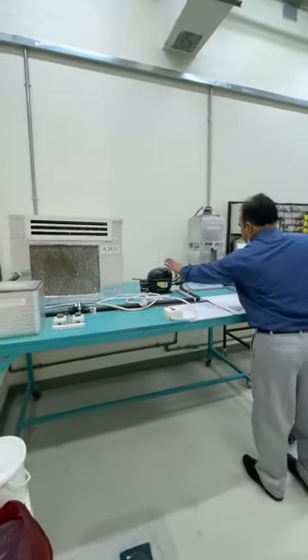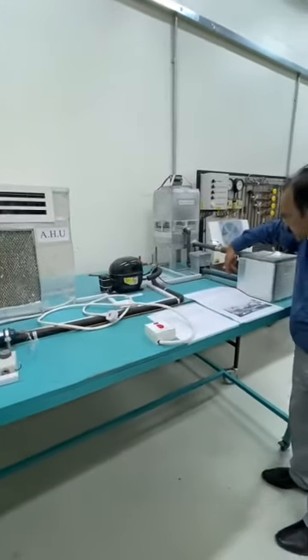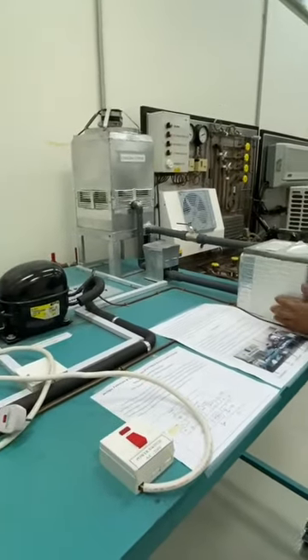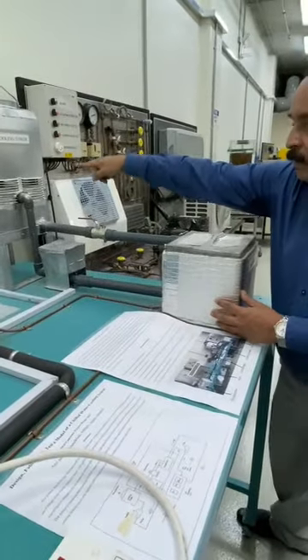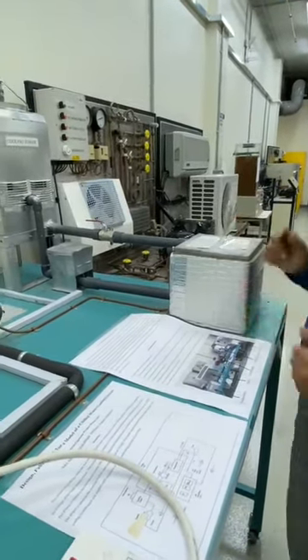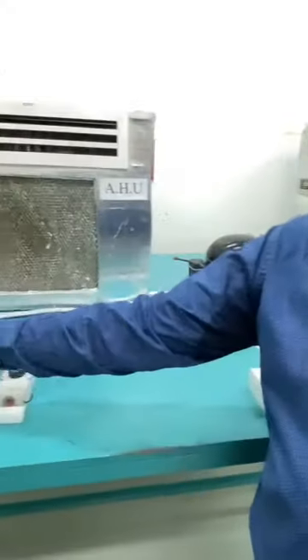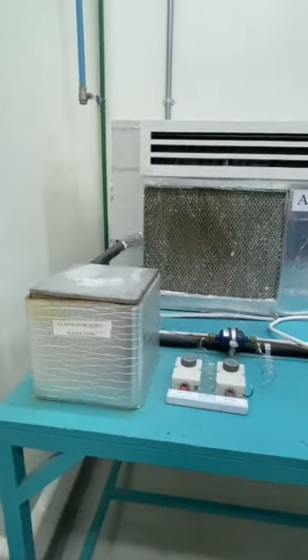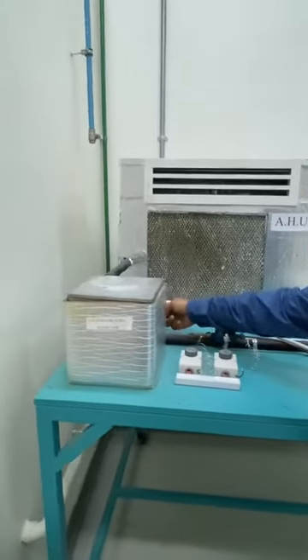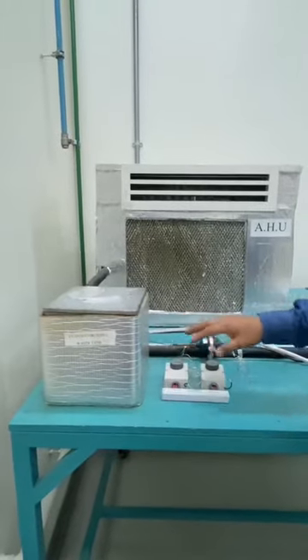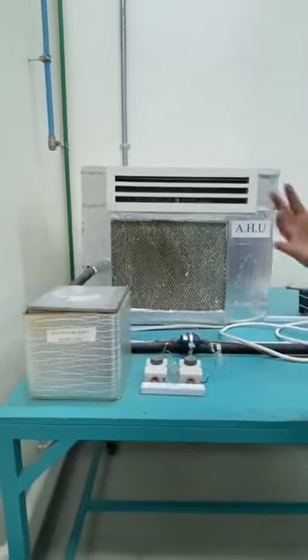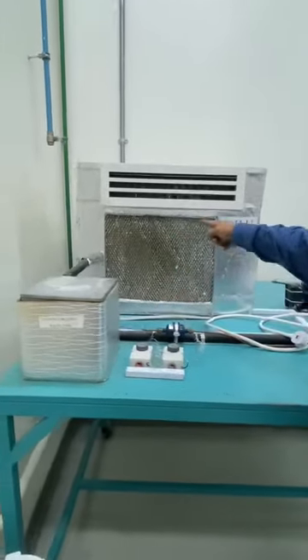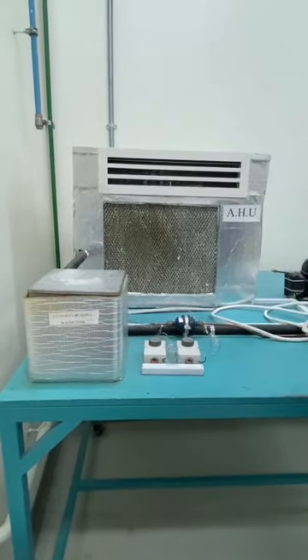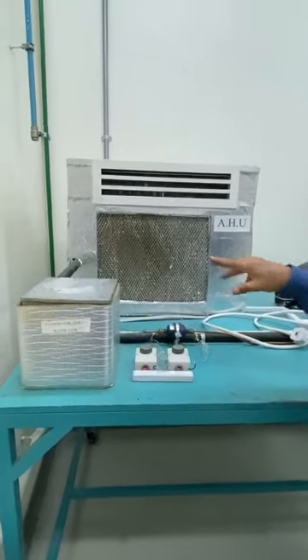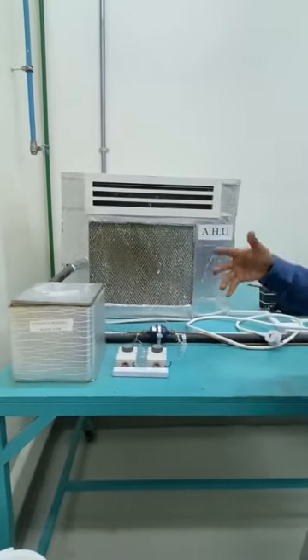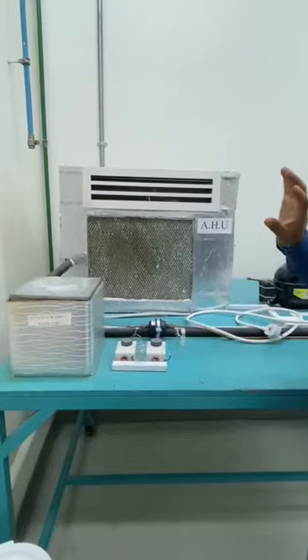So here what happens: the compressor compresses the refrigerant, and this refrigerant comes to the condenser here. The condenser will condense the vapor by the cold water coming from the cooling tower, and then the liquid refrigerant goes to the evaporator here. The evaporator also has a pipeline here, and then this liquid refrigerant goes to the chiller. The chiller will cool the water in the chiller, and then that chilled water will go to the AHU. When the blower blows air through the chilled water, the air gets cold, and that air is used for cooling purposes, distributed through the duct to the various buildings.